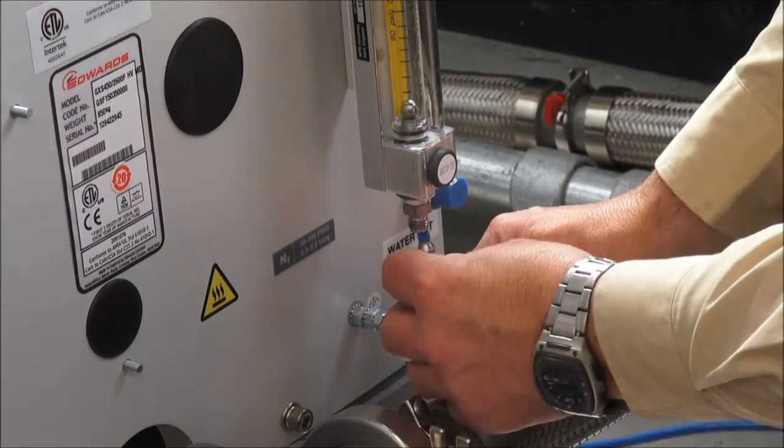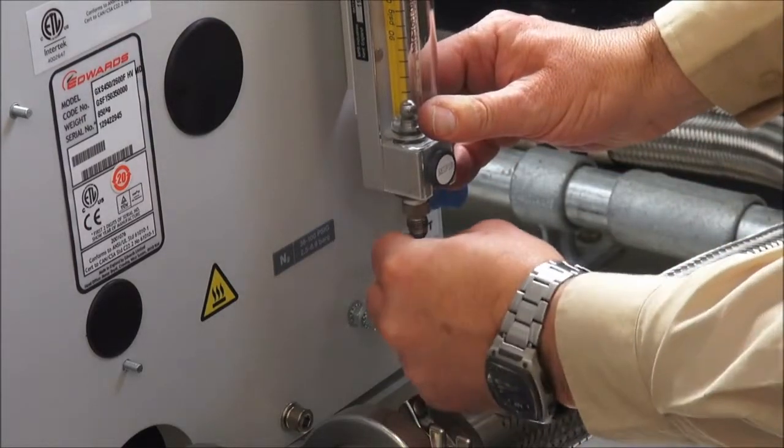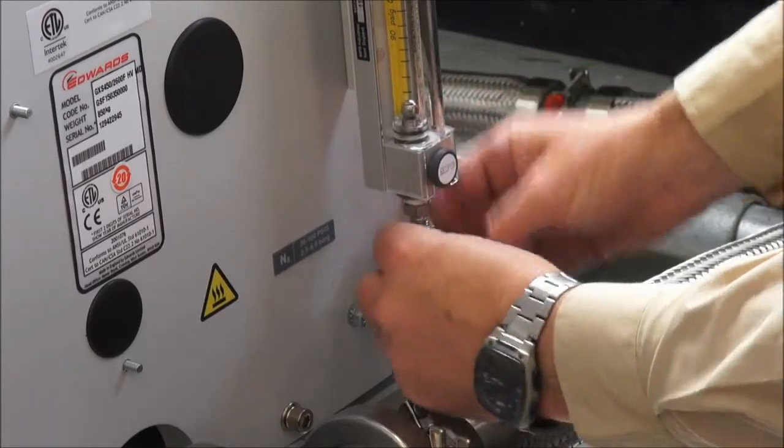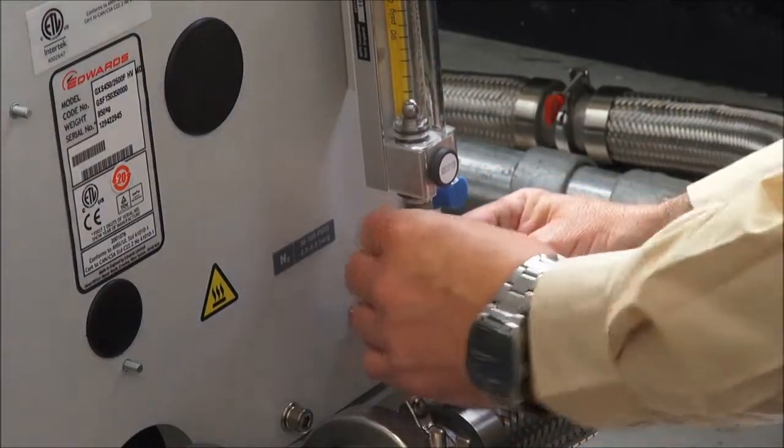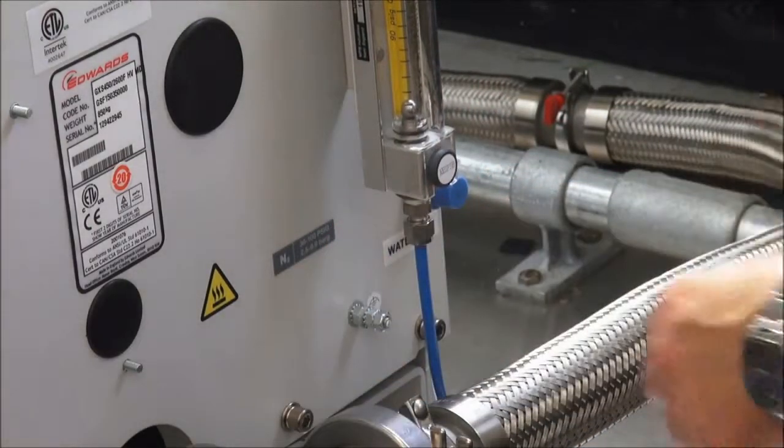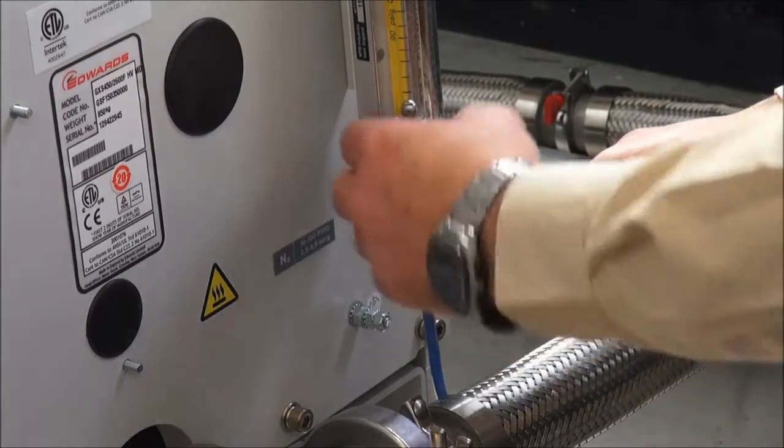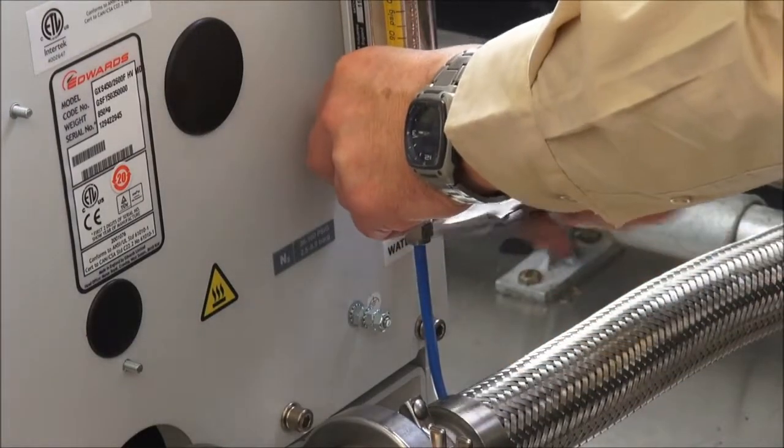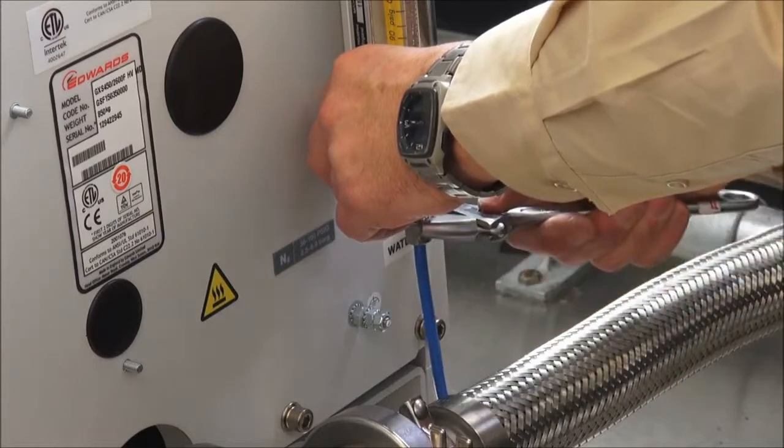Attach your gas supply. This would normally be dry nitrogen, but clean dry compressed air can also be used if appropriate for the application. The gas pressure specification is clearly marked on the label next to the rotameter connection. Tighten the connection properly.